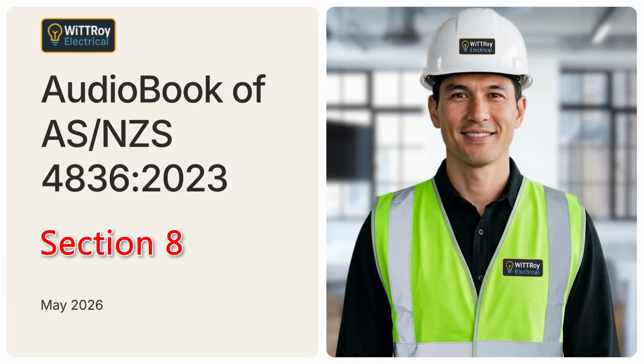An isolating transformer also has limits. It does not provide protection if the secondary winding is earthed. It does not provide protection if the tool contacts another electrical source, such as a concealed live conductor. It does not protect against electric shock between welding electrode and return leads. It also does not protect where the leakage path is between live conductors. In simple terms, RCDs and isolating transformers reduce risk, but they do not remove all risk. They must be used together with good work planning, correct tools, correct testing, and awareness of concealed conductors and other sources of supply.